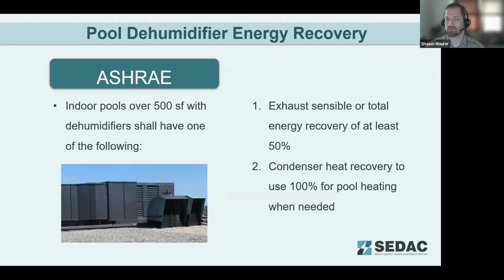ASHRAE also has some requirements for pool dehumidification. It's one of those areas that requires a lot of energy and can also increase chemical use if humidity is driven too low. So ASHRAE does require energy recovery at a fairly low threshold of only 500 square feet. It's likely that designs will select the first method listed here of exhaust sensible recovery or total energy recovery of at least 50%, because it's difficult to connect a condenser to the pool heating system. But it is possible to also do condenser heat recovery off of the pool system or the heat exchanger system and use that to provide heating for the pool when it's needed.